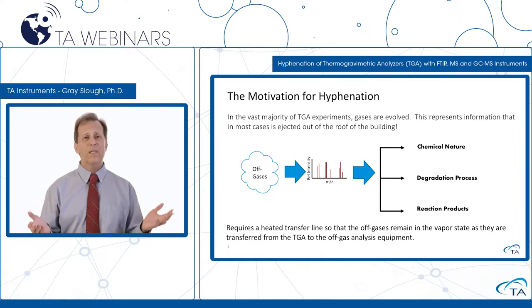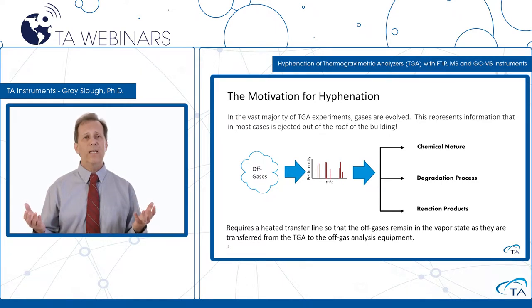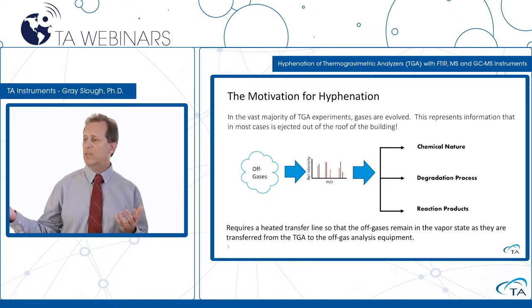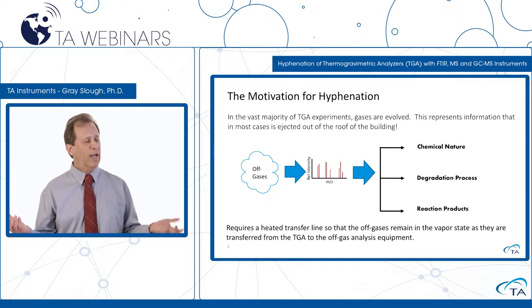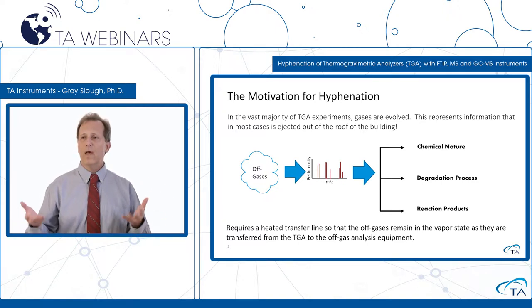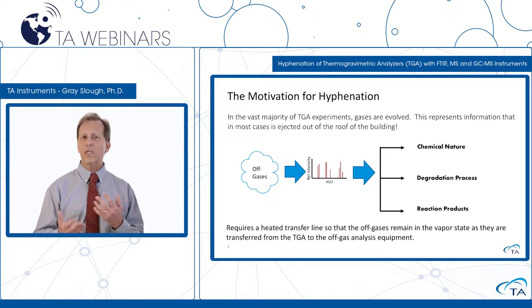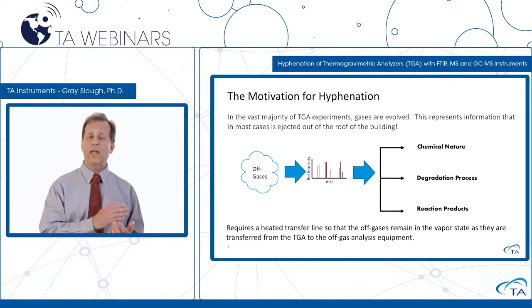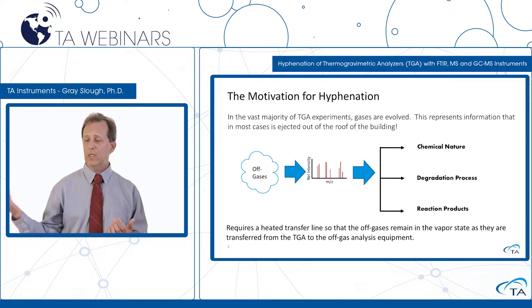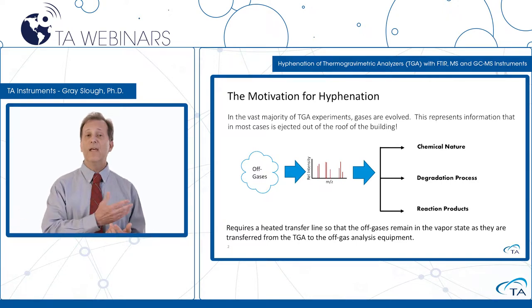The idea behind hyphenating a TGA with a spectrometer is to take those off-gases and do some type of chemical analysis on them, which could tell us something about the chemical nature of the sample, the particular degradation process occurring as the sample is heated, or potentially reaction products within the sample. Typically, this type of hyphenation just requires a heated transfer line attached to the TGA on one end and to the spectrometer on the other end, heated to keep the gases in the gaseous state as they proceed from the TGA to the spectrometer.